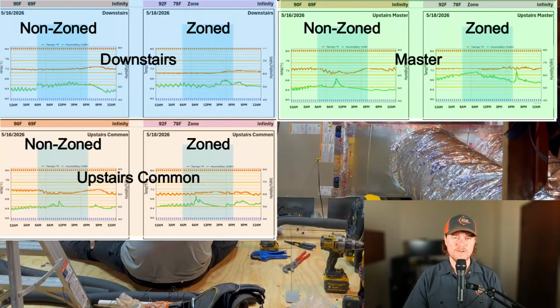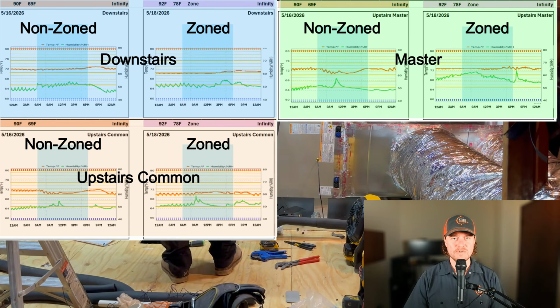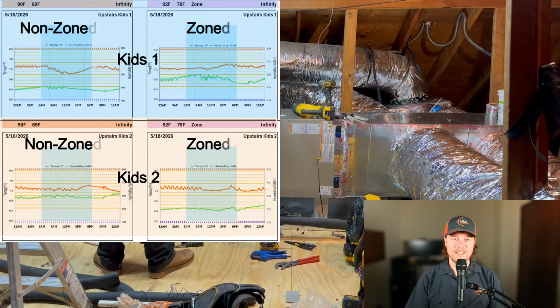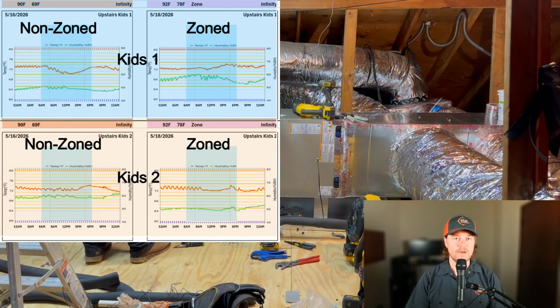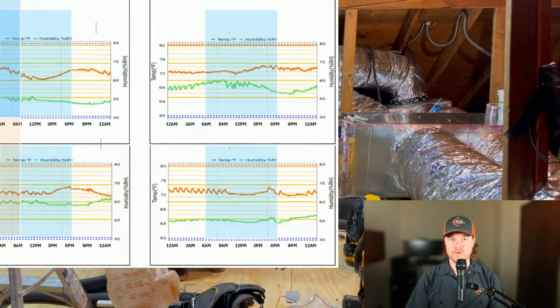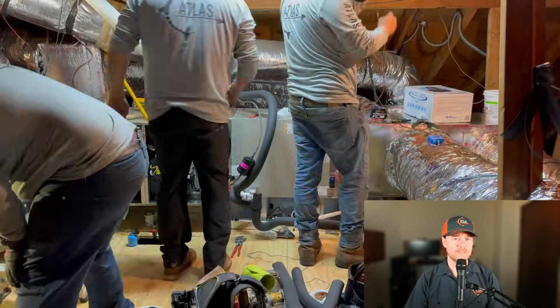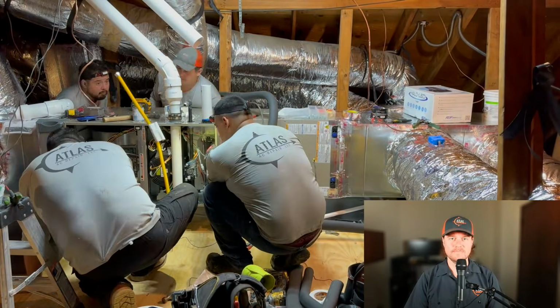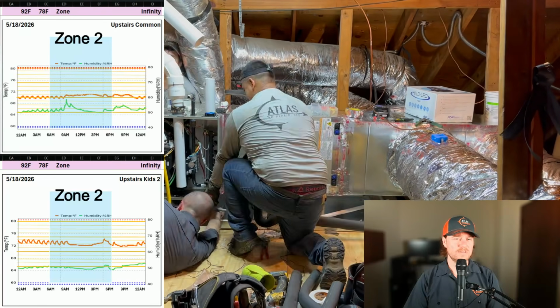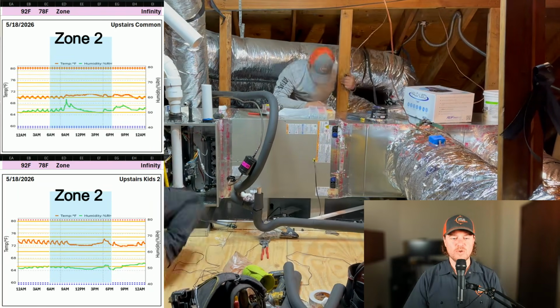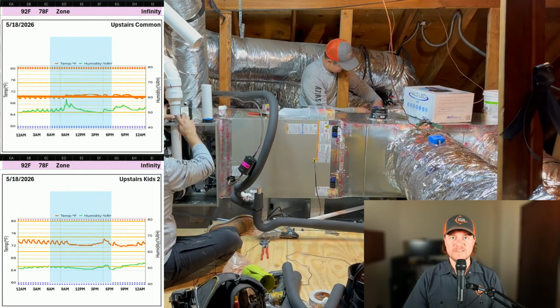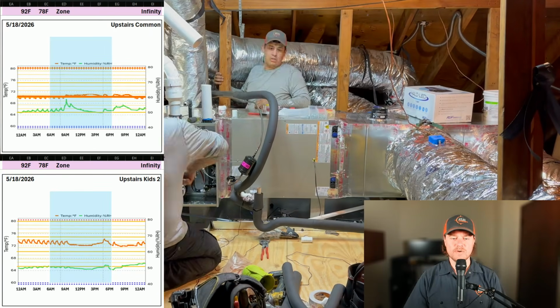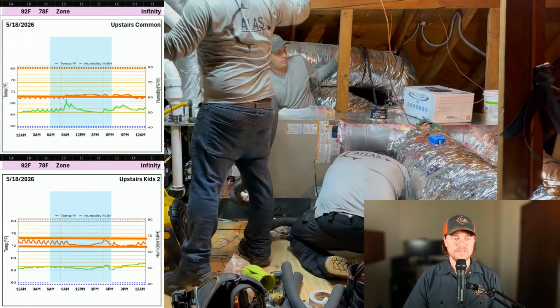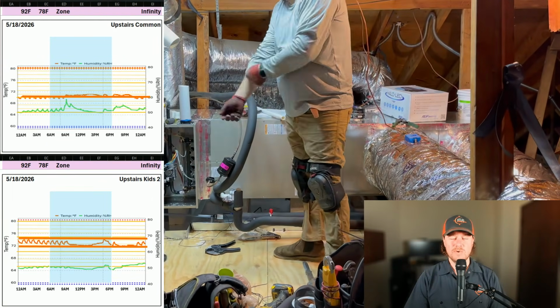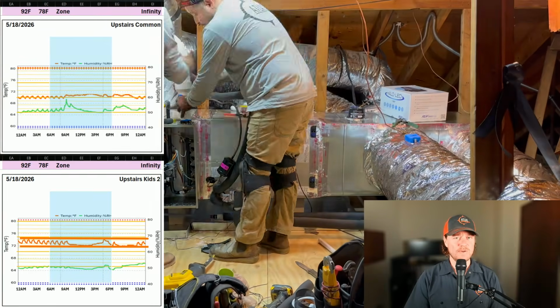And now with these modifications made, you can see every single room, both zoned and non-zoned, is pretty well balanced. That being said, the zone readings are coming back slightly better in almost every single space that I'm measuring, which makes sense because I have 3 thermostats that can just hit the nail on the head. I do want to point out my son's room, which is still a little off. In this example, I am running the zone system, and you can see that the upstairs zone is set at 70 degrees. However, in my son's room, it's still touching on 74 degrees, which isn't the end of the world and is well within HVAC standards.